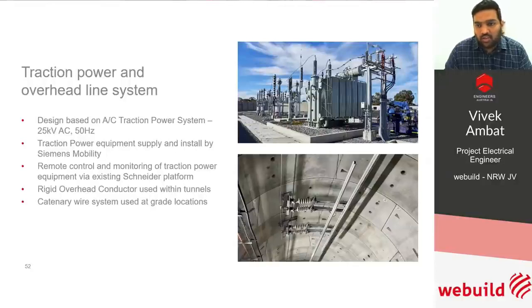To the right is our outdoor substation, where we get the 132 kV supply from the supply authority. This is reduced to a 25 kV single phase supply in the outdoor substation, and that green bit is the transformer, which reduces the voltage from 132 kV three phase to 25 kV single phase.